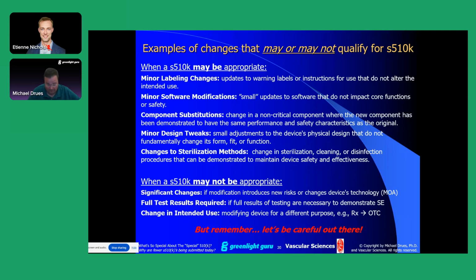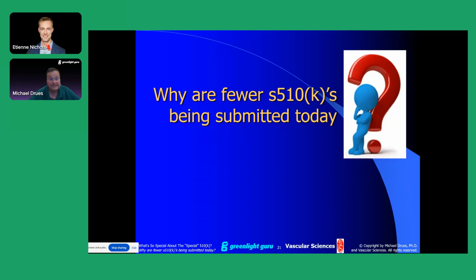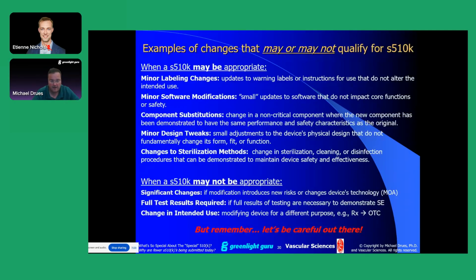However, let's be careful out there, because as we're going to talk about when we get to the letter to file, the single biggest reason why companies get pinged on manufacturing inspections is change control, or the lack thereof. In other words, they will submit a letter to file instead of a special 510K. And then FDA comes knocking on the door and says, hey, we don't think that this was appropriate to do as a letter to file. You should have notified us via a special 510K or possibly even a traditional 510K. And now you're in a whole bunch of problems. Unfortunately, this happens more frequently than a lot of people think.